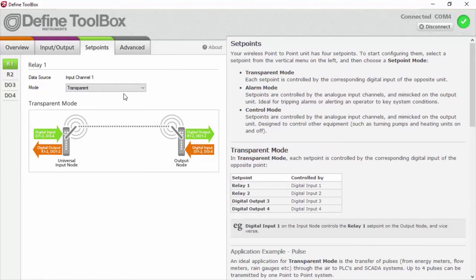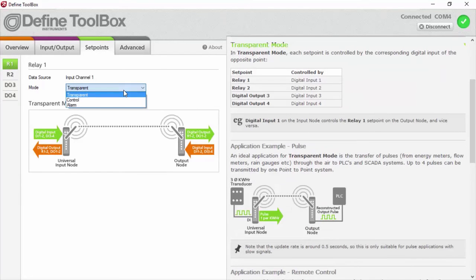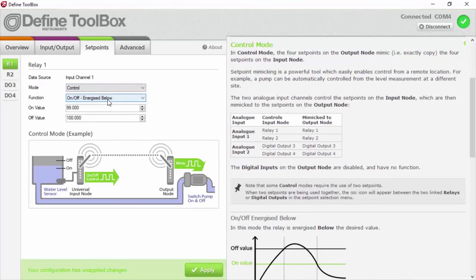So let's have a look at relay 1. We're going to use this to control our pump. It has a whole lot of different modes, but we put them into 2 categories of control and alarm. Because we're controlling a pump, control is the obvious choice. If I select this function drop down here, we can choose from a whole lot of different applications that we've programmed in. You actually see a diagram here as well for the different modes.